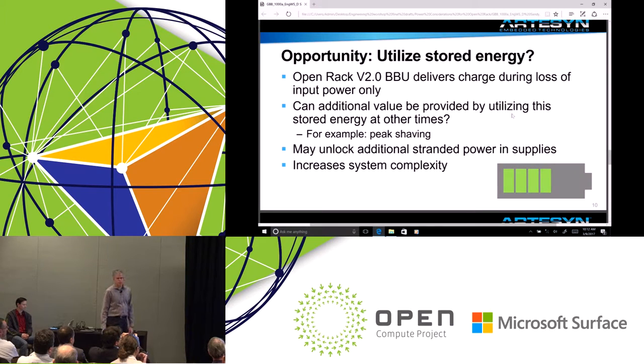Next slide. This one: can we utilize the stored energy in other ways? There's local energy storage within the shelf, primarily there to hold up the system in the event of catastrophic input feed failure - you're waiting for your diesel generators to come up, you hold up the power using the battery backup, the diesel generators come up, and the batteries start charging again. So it's just the fail-safe there. But if you have the batteries in there with some changes to the system, you can use that spare battery capacity potentially to do things like peak shaving. Not a new concept, but not one that's currently implemented.